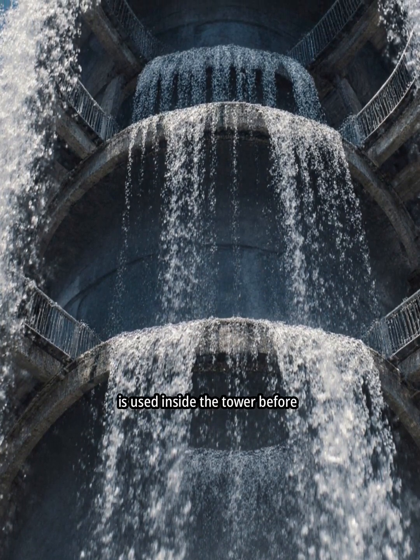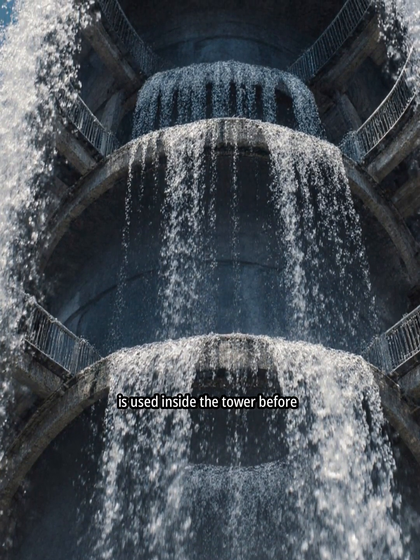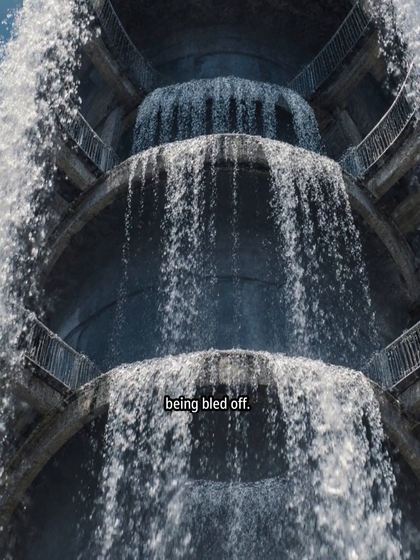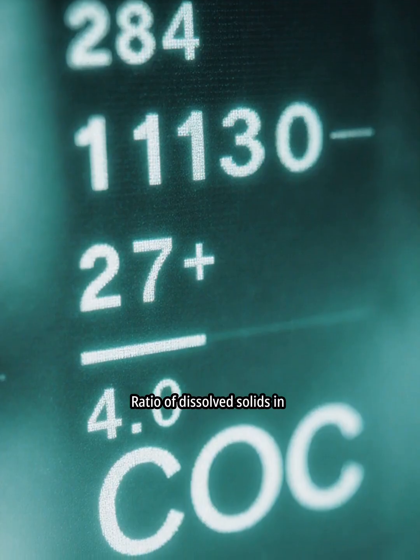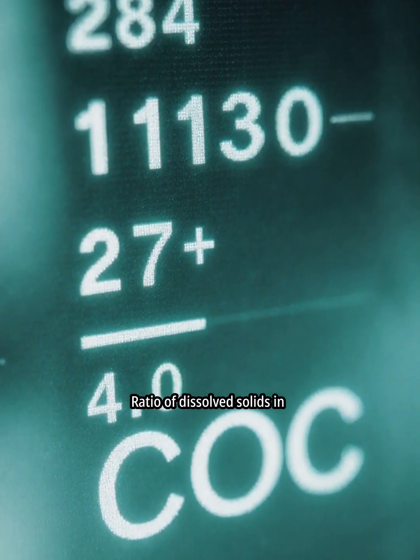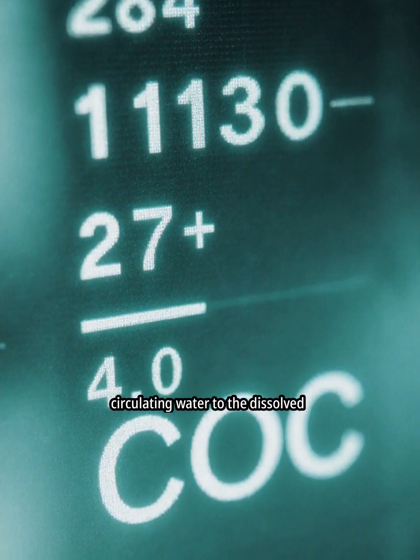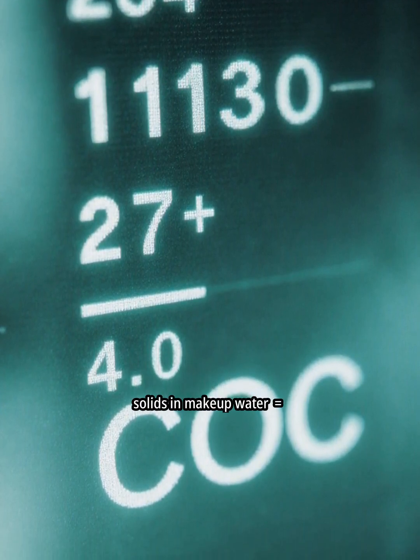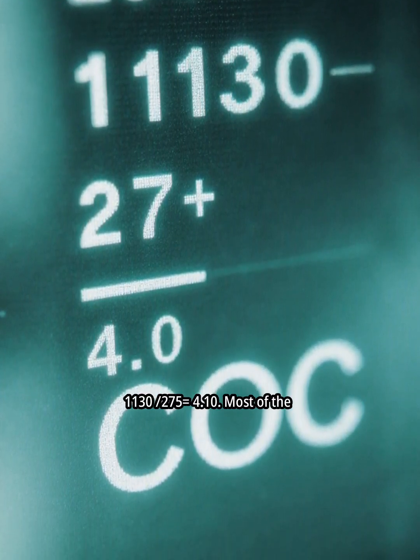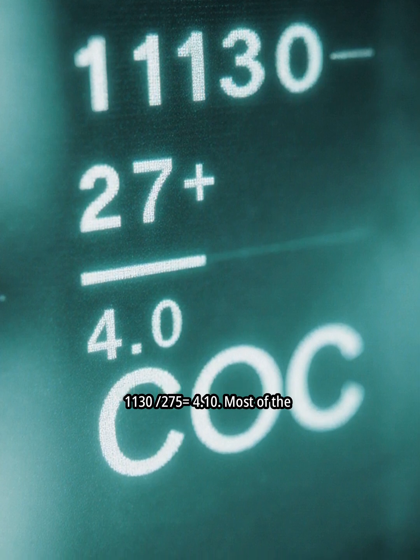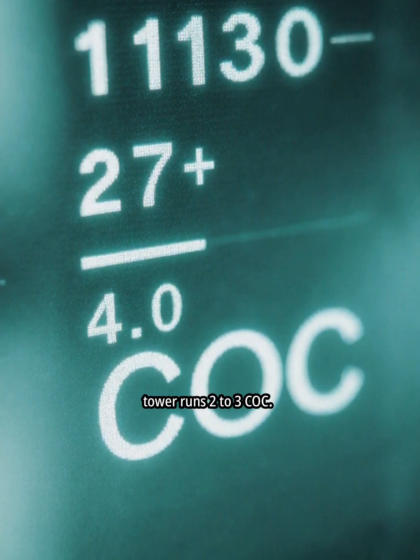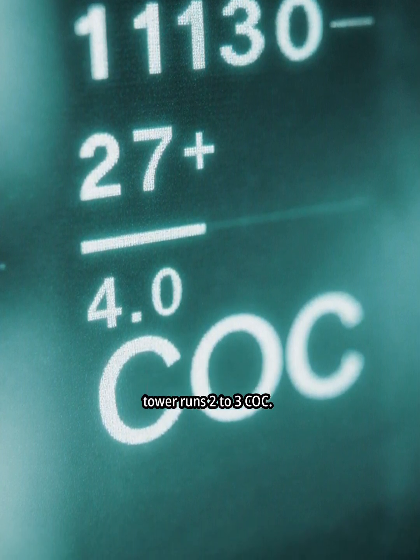COC. It is how many times water is used inside the tower before being bled off. It is the ratio of dissolved solids in circulating water to the dissolved solids in makeup water, equals 1,130 divided by 275 equals 4.1. Most towers run at 2 to 3 COC.